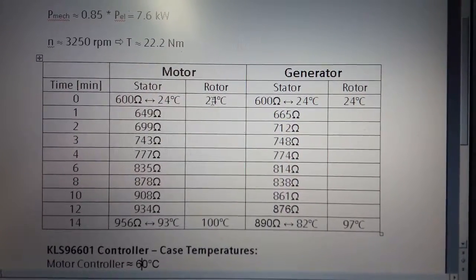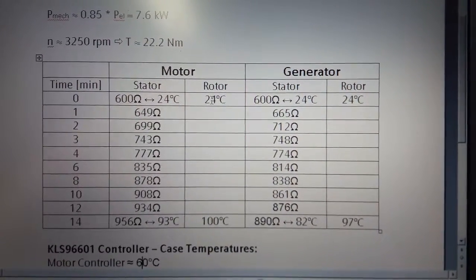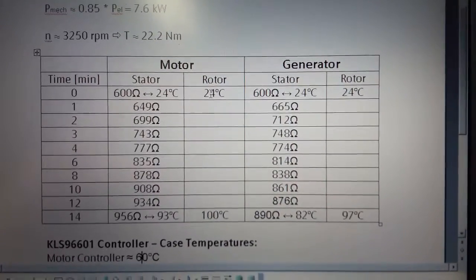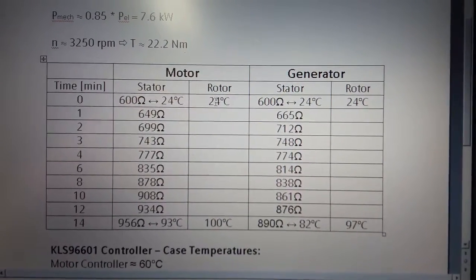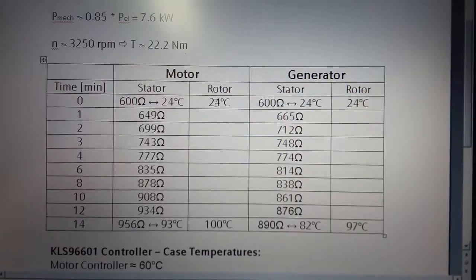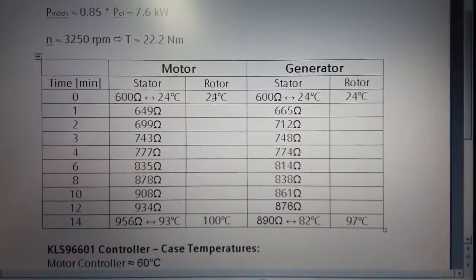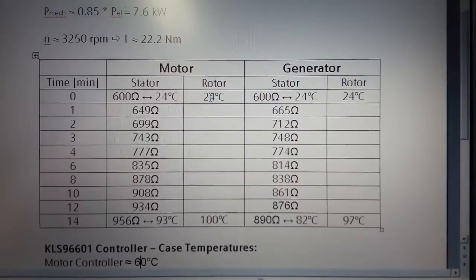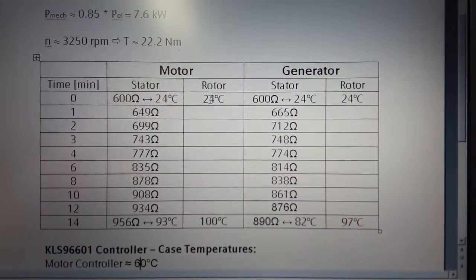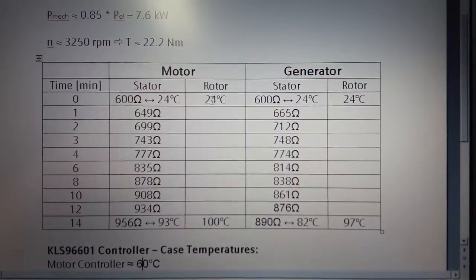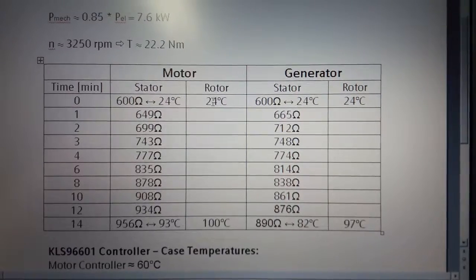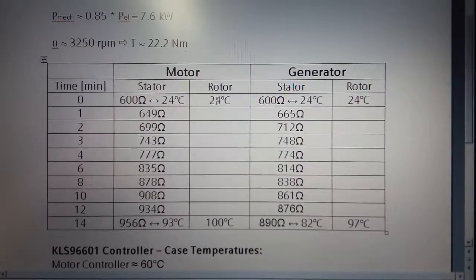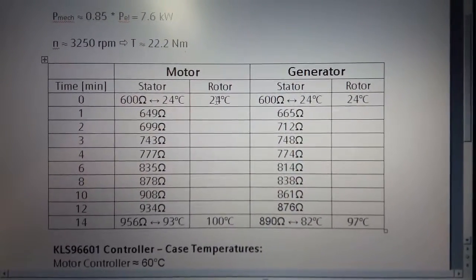Both values are totally fine according to the manufacturer who says 120 degrees continuously. The rotor is a little bit more critical. The motor rotor temperature was finally at 100 degrees Celsius and the generator at 97 degrees Celsius, which is short time operation only according to the manufacturer.